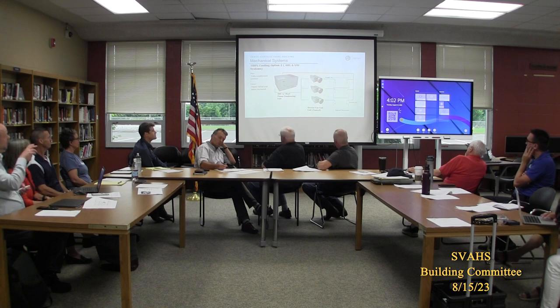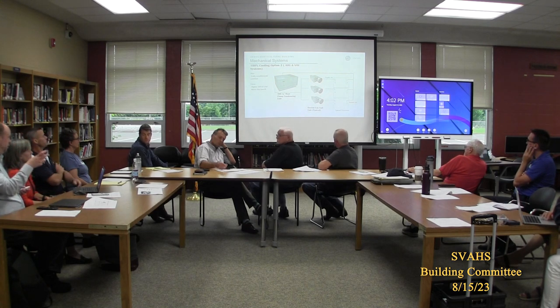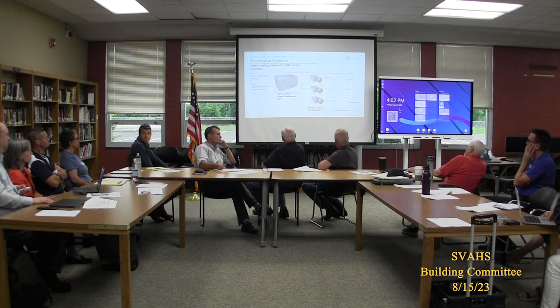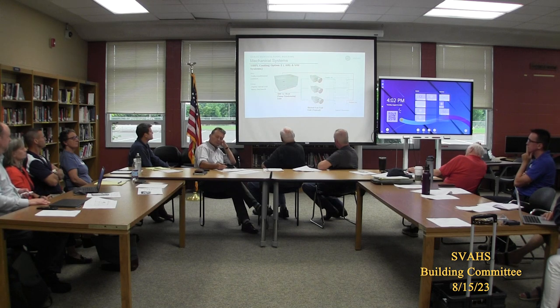The other way of thinking about this system is you can take the air handling unit and put it inside the building, hanging it above a ceiling or on the floor, but it takes up space, so we don't necessarily want to go that route. We want to make sure it's not positioned over any learning environment, because these can get noisy, and even with a ceiling, that noise can translate through and be distracting for educational environments.